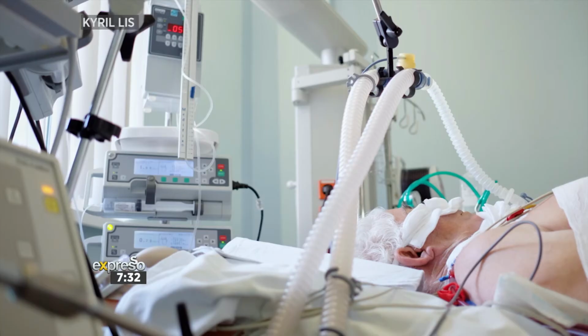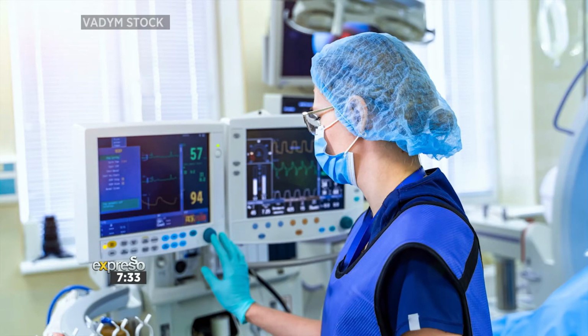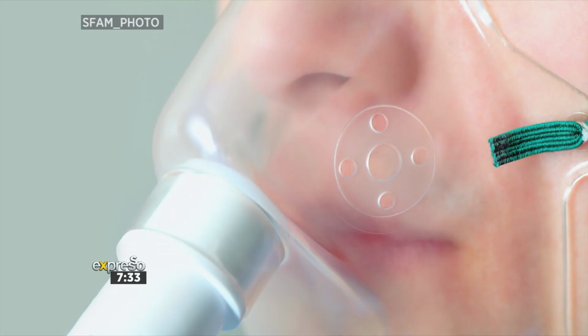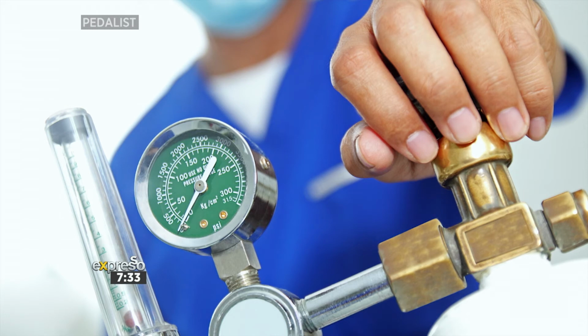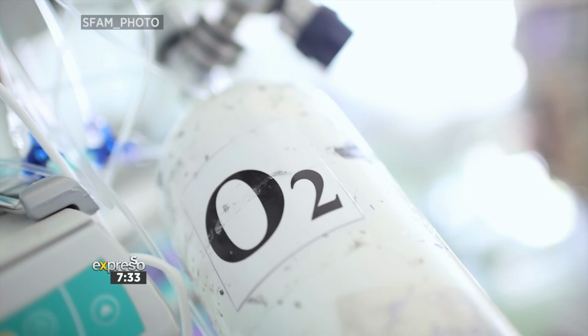Now, let's talk about what's happening right now in terms of trials testing the efficiency of the machine that have begun at UKZN. What are the results that you are getting from there? Has there been positive feedback? Yes. Well, we have tested it on what is known as a gas analyzer, and the device performed very well. It gave the correct breathing rate, and it gave the correct volume, and the doctors wanted it turned right up to 100% oxygen, and we found that there was 100% oxygen being delivered by the device. So we seem to have met the specifications required, but the device hasn't been through the regulatory authority testing yet.